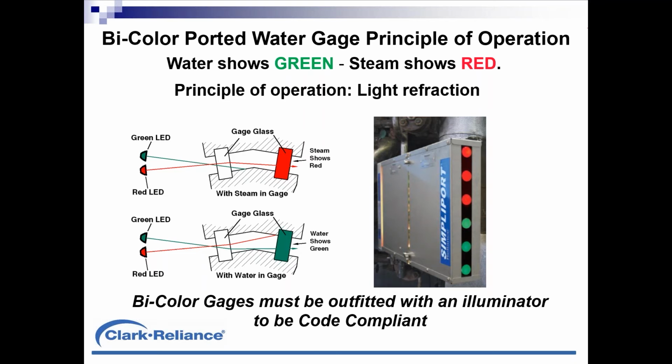The other thing I'd like to note is if you're using a ported gauge and you begin to see a red crescent moon in what should be all green as the gauge has changed, so to speak, that's a sign of deterioration on the mica shields on the inner side of the glass or dirt within the gauge, contamination. The first plan of attack should be to blow down that gauge glass and see if the sharp greens return fully. If not, it might just be time to rebuild that gauge.